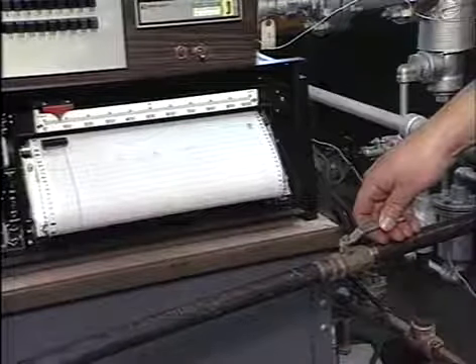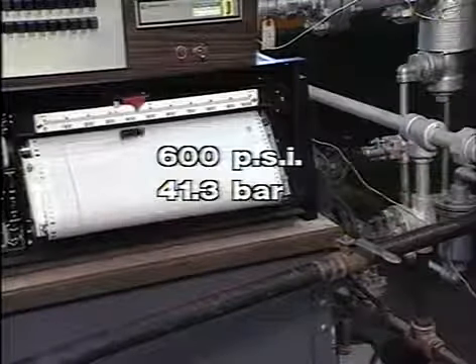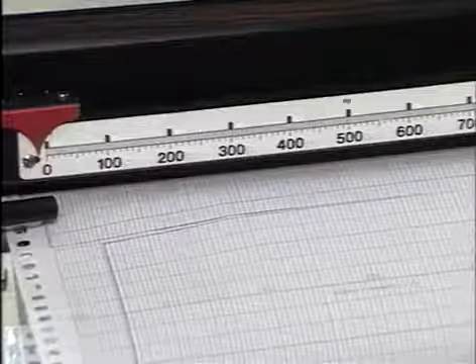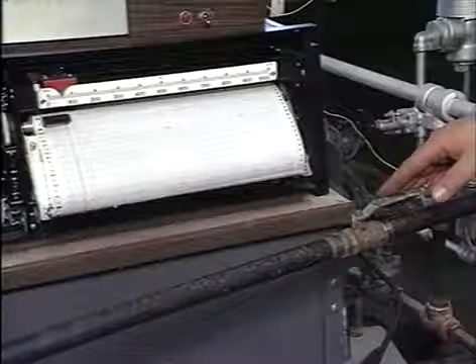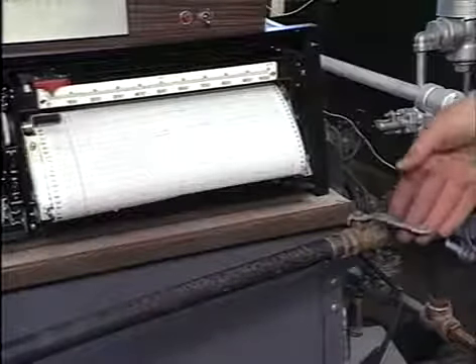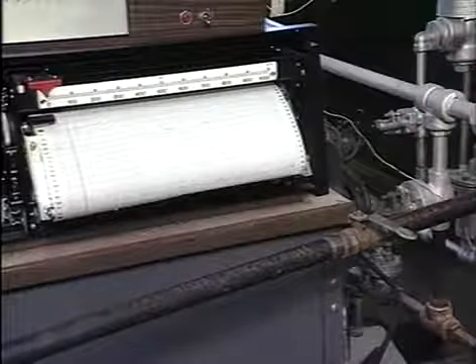A shock wave of about 600 psi slams into the valve and rebounds in all directions, expanding the piping and reflecting back and forth along the length of the system until its momentum is dissipated. By closing the valve slowly, the velocity of the water is reduced before the column is stopped. Since the momentum of the water is decreased gradually, damaging water hammer will not be produced.